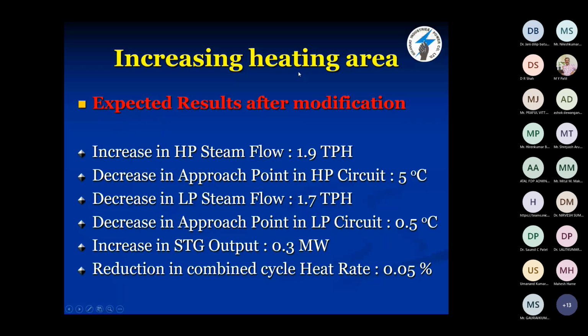So after increasing the heating area, the expected results were an increase in HP steam flow. It was 1.9 ton per hour, the increase in the steam flow. The decrease in approach temperature, earlier it was 16, now it has decreased by 5 points. Decrease in LP steam flow, 1.7, because we have increased the heating surface.